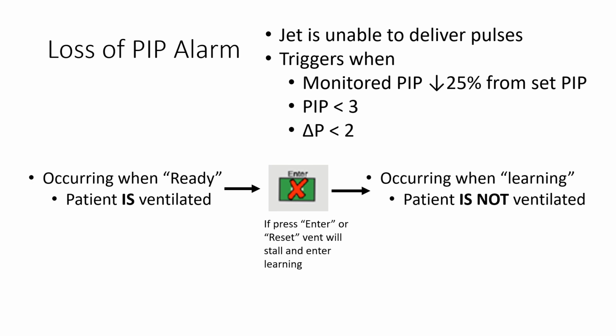The loss of PIP alarm can occur while the jet is in the ready and non-ready condition. When in the ready mode, breaths will still be delivered to the patient and the alarms will be active. In the non-ready mode, no flow will be delivered, the alarms will not be active, and the patient will not be ventilated. If the loss of PIP alarm occurs in ready mode, the ventilator will deliver breaths based on previously established pressures. However, the monitored values of PIP, delta P, and mean airway pressure will be incorrect.